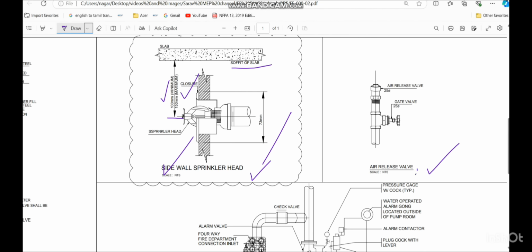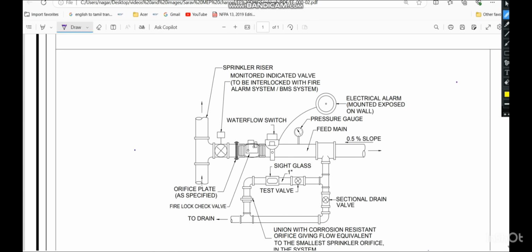The next one is the air release valve. I showed we install the air release valve in the top of the riser. So we have to provide one 25 mm gate valve, and after that we have to do the air release valve, because if you want to do any maintenance in the air release valve, we can isolate using the gate valve. The next important installation in the firefighting system is the zone control valve.